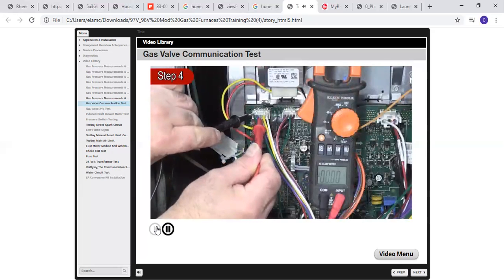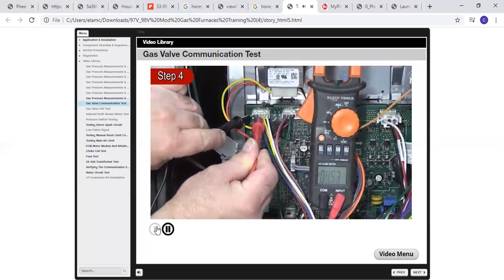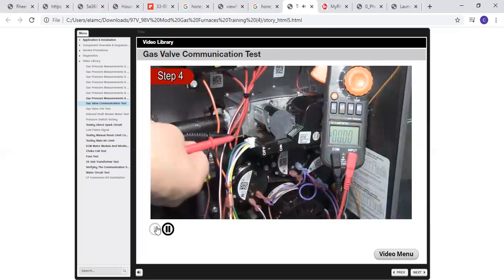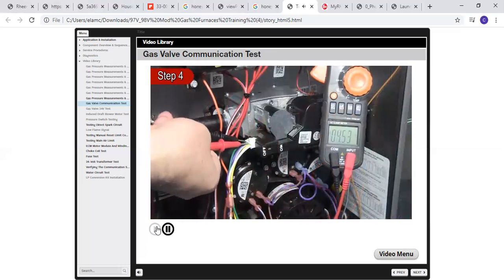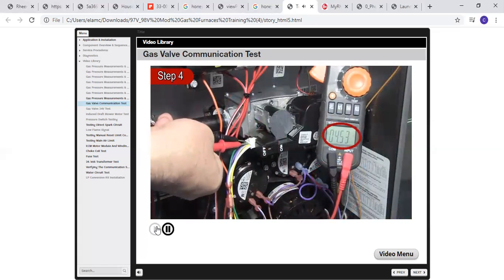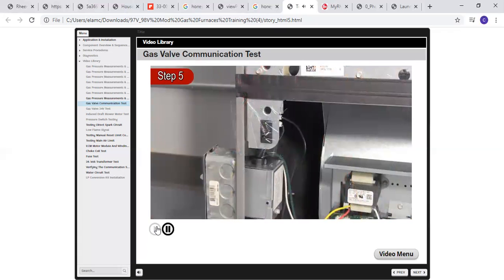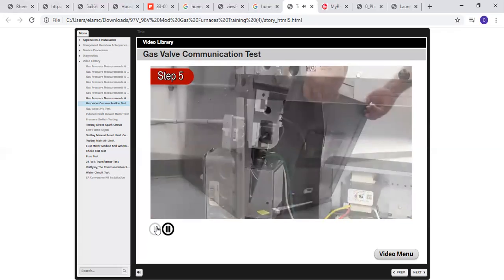Step 4. Check for DC voltage between the receive and ground pins at the control board, gray and green wires. If 3 to 5.5 volts DC is present, the board is receiving communication from the gas valve. If the voltage is not present, check for transmission voltage at the gas valve pins, gray and green wires. If voltage is present, the wiring is open between the gas valve and the integrated control board. If voltage is not present, replace the gas valve. Step 5. When testing is complete, release the door switch and reinstall the furnace blower door. Now we'll proceed to the 24 volt gas valve test.